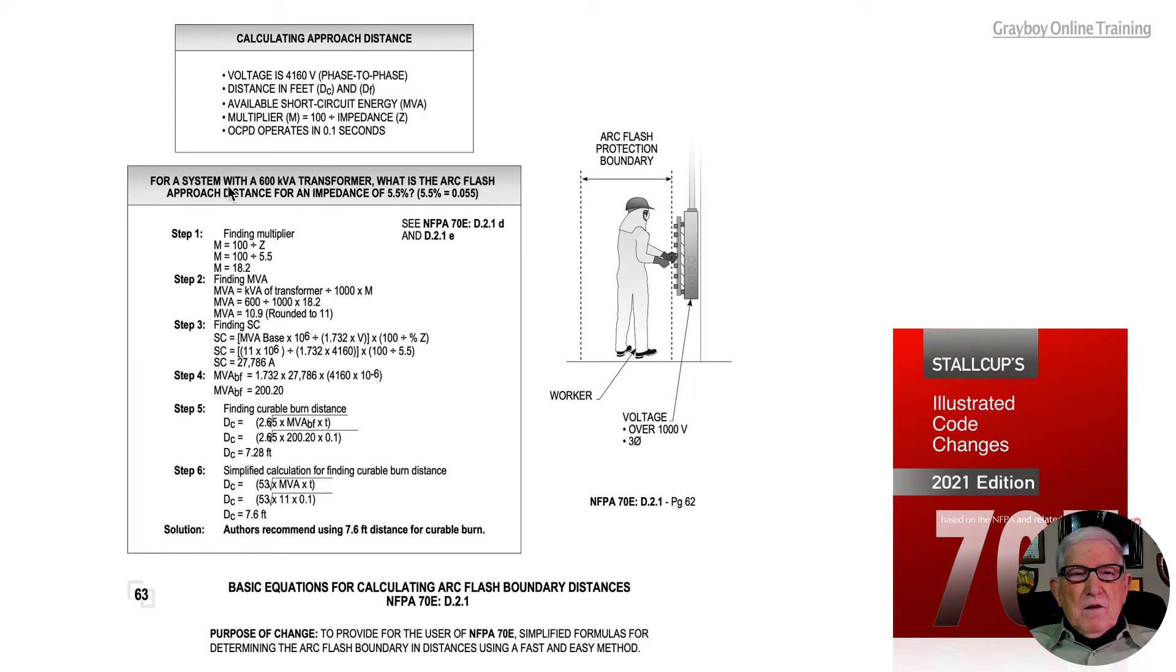For a system equipped with a 600 kVA transformer, what is the arc flash approach distance for an impedance of 5.5 percent? When that's converted it's 0.055. Now to determine step one, we're going to go through it in accordance with Annex D.2.1d and D.2.1e.